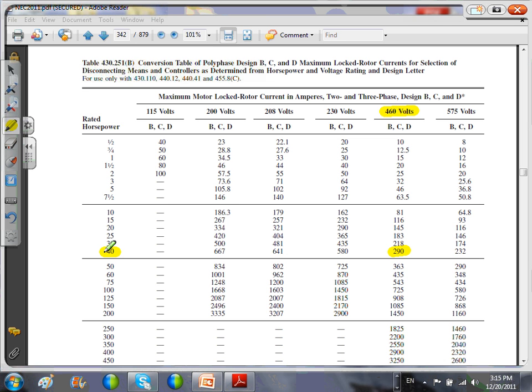So they add the locked rotor current, and then they come to this table under the right voltage, because you have to have the right voltage. If it's 290, it corresponds to 40 horsepower. So when you go buy your horsepower motor disconnect, you're going to say I need a 100 amp or 200 amp horsepower, depending on the size, and also rated to interrupt. It's not going to explode if somebody accidentally disconnects under load. Rated for 40 horsepower. Any questions, guys?